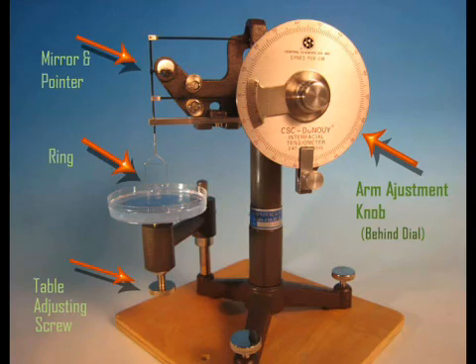To perform the test, there are a few key parts of the instrument. The mirror and the pointer indicate the effect of surface tension forces on the ring as it passes through the sample surface.